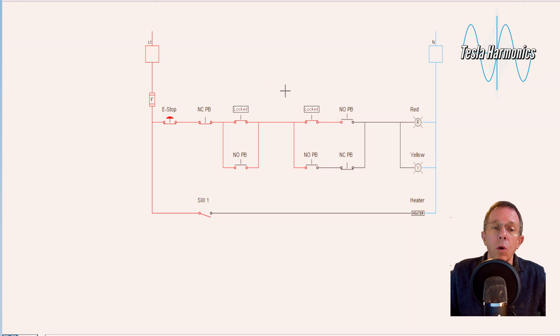All of the inputs can be wired in series, series parallel, however we want to wire them. But because of voltage drops, we don't put the outputs in series. We put them in parallel or we put them on a separate rung where the heater is, and I can turn it on and off the same way.